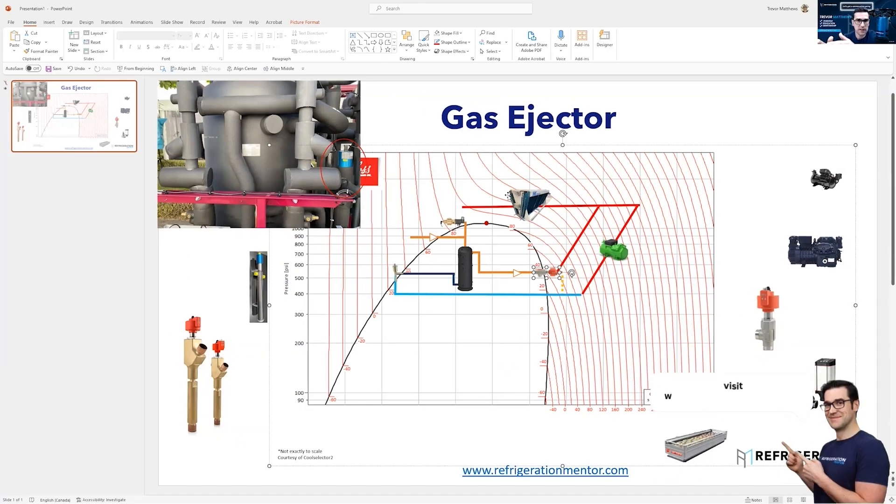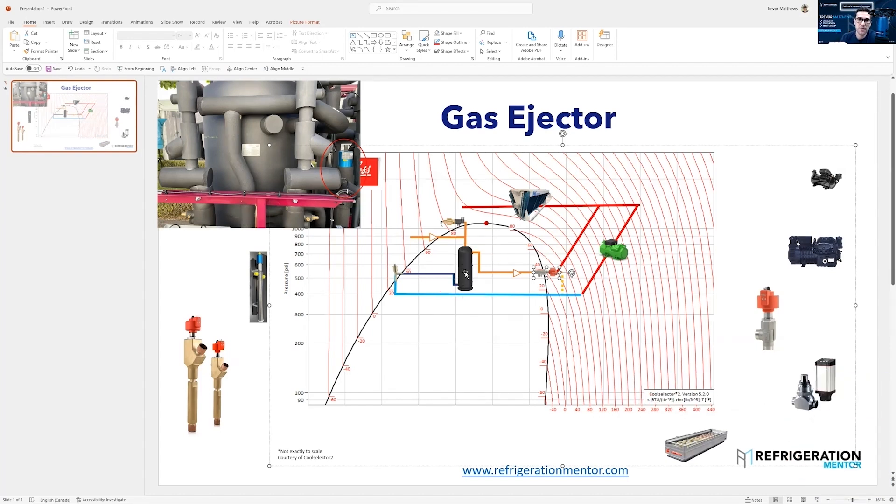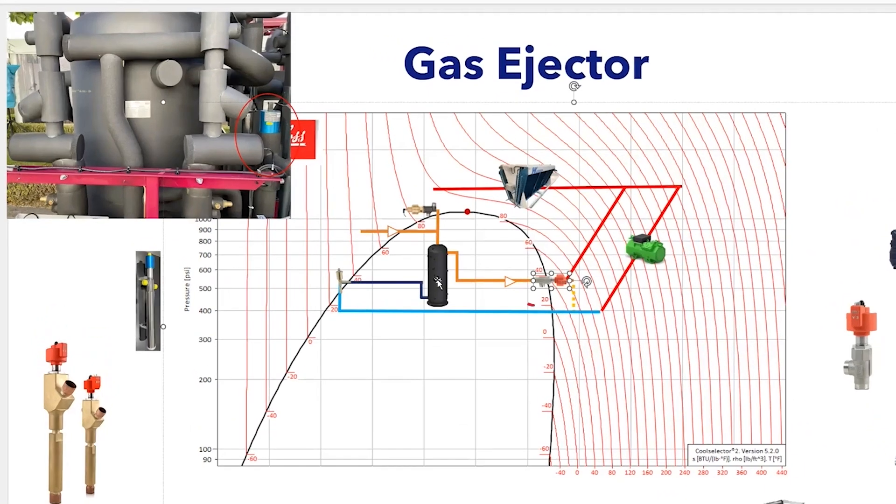In the middle of summer, when it's really warm out, you got way more flash gas than liquid. Inside the flash tank receiver, you're getting a higher percentage of vapor than liquid. That means this valve is doing a lot more work. These medium temp compressors are doing way more work.